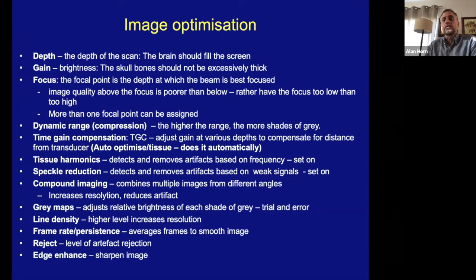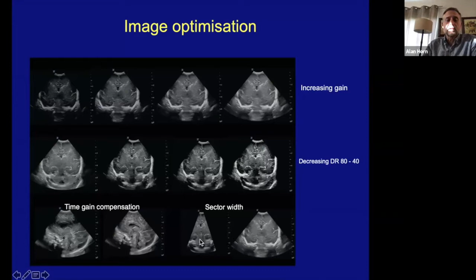And here we see the effect of increasing the gain from just right to too much, from decreasing the dynamic range from just right to too little, where we get fallout around the edges, and from having an incorrect time gain to a correct one. And the other thing is the sector width, if it's too wide and you're getting fallout, or if it's too narrow and you aren't seeing what you need to see.